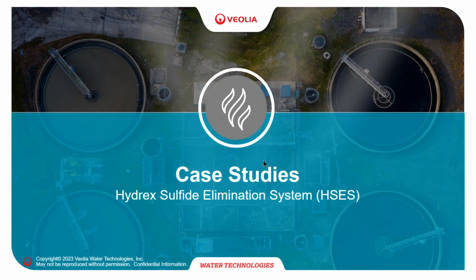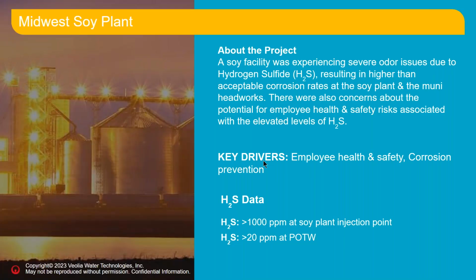Now I will quickly share some case studies where we've utilized the Hydrex sulfide elimination system, both in municipal and industrial settings. We will, of course, not share the client's name or any other sensitive information. I'm going to keep it very general. In this project, a Midwest soy producer was experiencing both H2S odor complaints as well as physical damage to their process equipment in the plant. So both safety and equipment protection was important. Before our treatment, the H2S in the air above the water was over 1,000 ppm at the injection point and over 20 ppm at the city's water reclamation facility downtown.